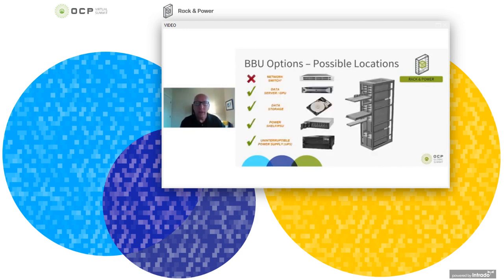If we take a look at a virtualized system, as I'm showing here, essentially you can get battery backup in each one of these particular modules with the exception of the network switch. That's part of the challenge for the system architect: determining the concerns with the amount of runtime required, latency issues within the system, what type of voltages, and what the power architecture already is in that system. So what you don't want to do is be redundant if you don't need to, but when you have a clean sheet of paper, you have to decide where you want battery backup to reside.